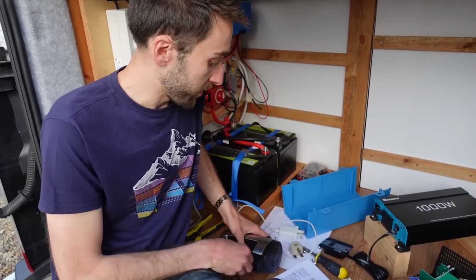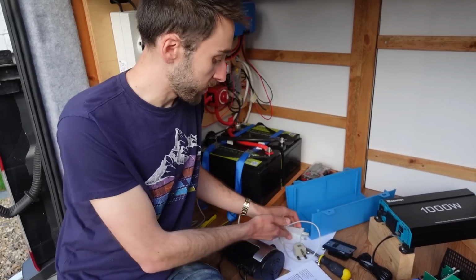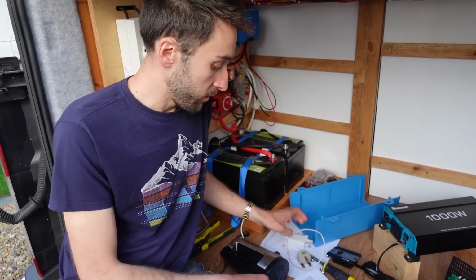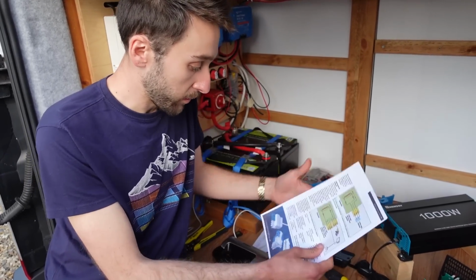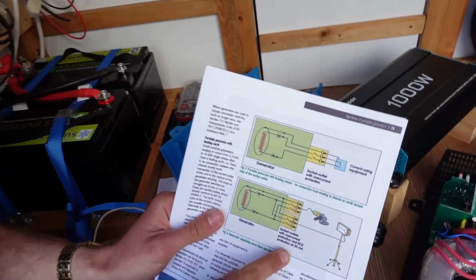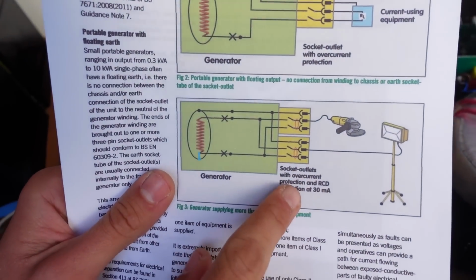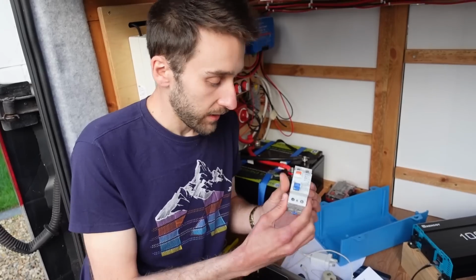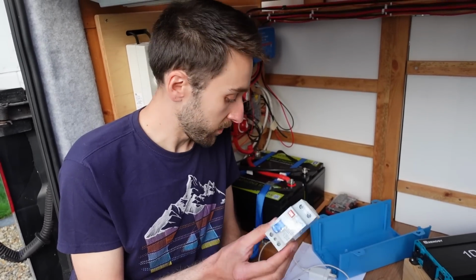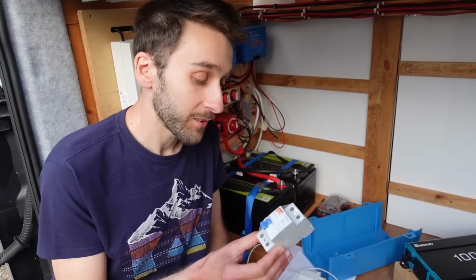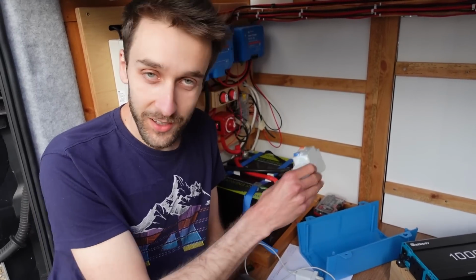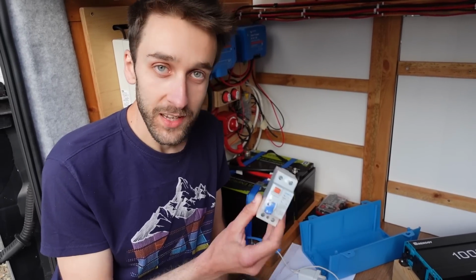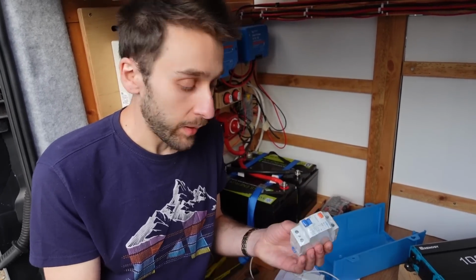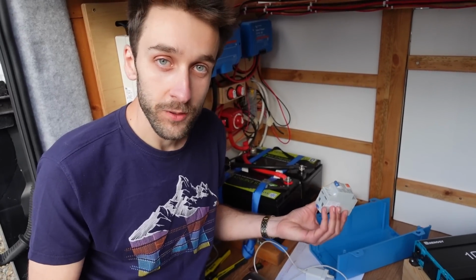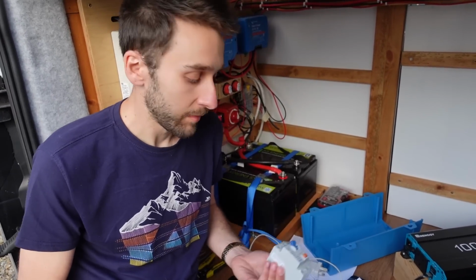With class 2 devices, you can't really have that problem because they're all insulated really well. So if you do want to use multiple class 1 devices, you need an RCD to provide protection. An RCD is a device like this, and all it's really doing is making sure the current isn't going where it shouldn't. If the current doesn't follow the normal path in the circuit, it will detect that and trip, cutting the power, hopefully before it causes any injury or worse to whoever's touching it.